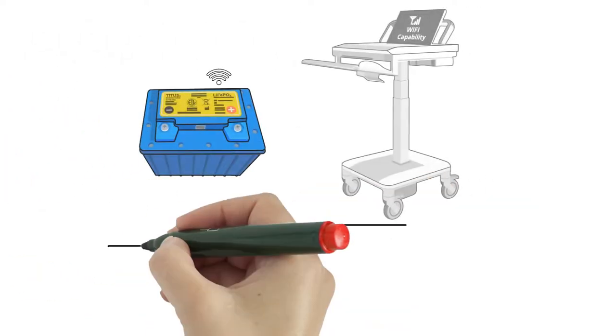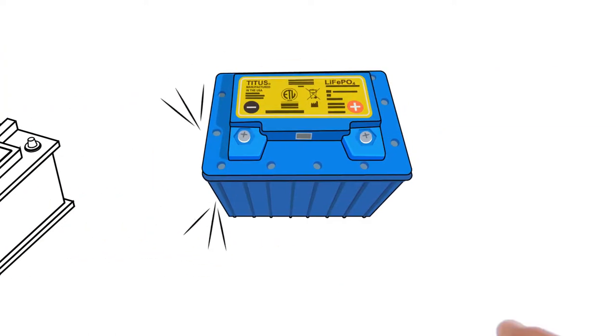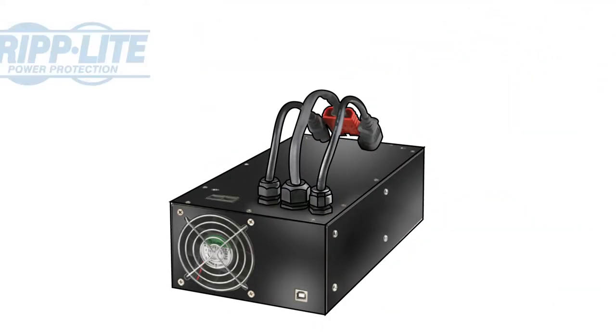The key benefits are state-of-the-art wireless communication system, remote diagnostics, drop-in replacement for U1 lead-acid batteries, communicates with inverter, chargers made by Tripp Lite and PowerVar communications.